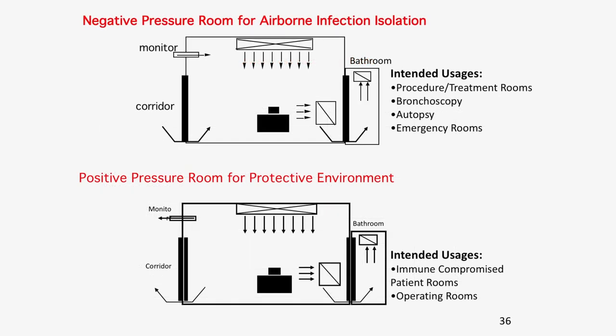The various rooms in slide 36 are conceptual, dealing with the principles of negative or positive pressure, depending on what you're trying to achieve. The air change rates are the same. Pressure management ideally should be somewhere around 5 pascals or greater, but not too much—some countries use 30 pascals, which is enough to suck the paint off the walls. And if it's under negative pressure, it's enough to start capillary movement of water if the facade isn't put together properly in the curtain wall.